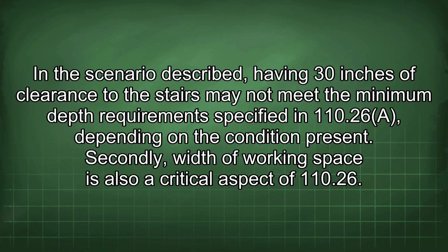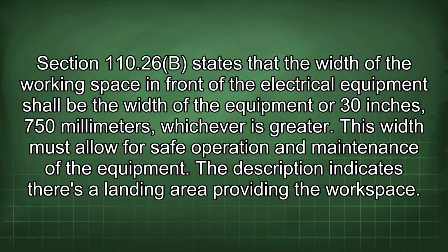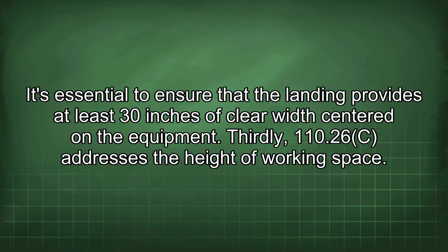Secondly, width of working space is also a critical aspect of 110.26. Section 110.26b states that the width of the working space in front of the electrical equipment shall be the width of the equipment or 30 inches, 750 millimeters, whichever is greater. This width must allow for safe operation and maintenance of the equipment. The description indicates there is a landing area providing the workspace. It's essential to ensure that the landing provides at least 30 inches of clear width centered on the equipment.